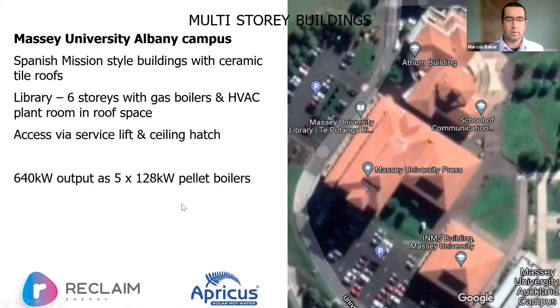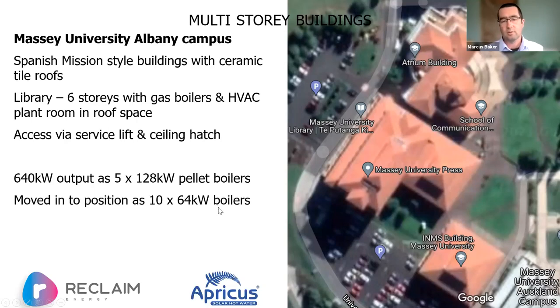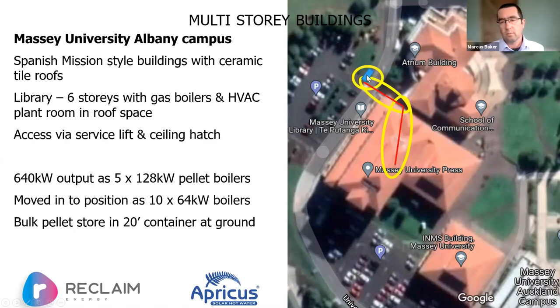So we've designed in a system with 640 kilowatts of boilers in this rooftop plant room, made up of five lots of 128, which breaks down to actually 10 64s for getting them physically up here, because that's a significant challenge all on its own. And then delivering the pellets, we put a bulk store here at ground level. I mean, it could be anywhere, but this was just a bit of dead ground. And then an underground delivery pipe, which pops up just outside and beside the building.